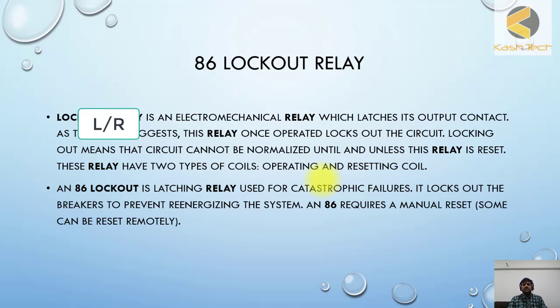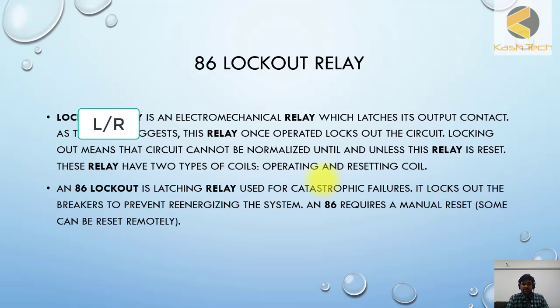Lockouts are operated when there is some severe fault. For example, in a protection zone, when a heavy fault occurs, the lockout operates and somebody has to come and reset it physically at the protection panel. After careful checking, the lockout can be reset and the breaker can be closed. When a lockout is operated, the breaker cannot be closed from local or remote.